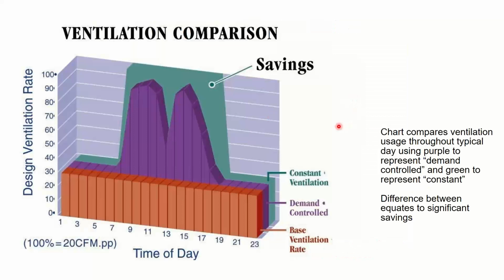This is what that's going to look like for your building or your school. This is actually an old chart from the 90s that we made, and I still keep using it because I'm too lazy to make a prettier one. But on this bottom scale here, the horizontal scale, is time of day from midnight to midnight. So each one of those is an hour band. And then up the left-hand side is my ventilation rate, with over here being no ventilation, and up top where it's 100 being my design ventilation. Whatever the building designer, architect, engineer calculated that I needed for fresh air in the building, that's this level right here.